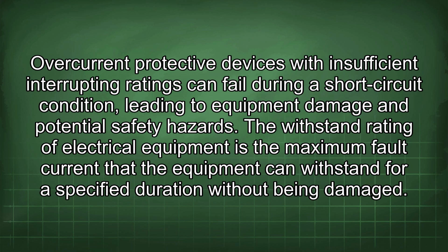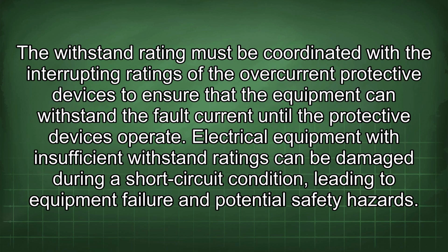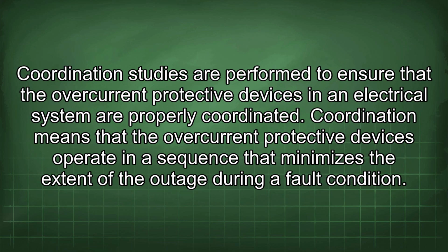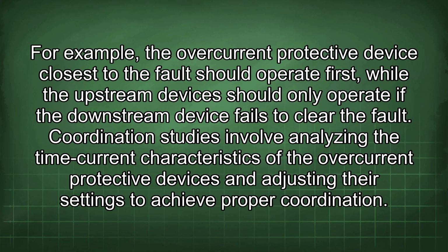The withstand rating of electrical equipment is the maximum fault current that the equipment can withstand for a specified duration without being damaged. The withstand rating must be coordinated with the interrupting ratings of the overcurrent protective devices to ensure that the equipment can withstand the fault current until the protective devices operate. Electrical equipment with insufficient withstand ratings can be damaged during a short-circuit condition, leading to equipment failure and potential safety hazards. Coordination studies are performed to ensure that the overcurrent protective devices in an electrical system are properly coordinated. Coordination means that the overcurrent protective devices operate in a sequence that minimizes the extent of the outage during a fault condition. For example, the overcurrent protective device closest to the fault should operate first, while the upstream devices should only operate if the downstream device fails to clear the fault.